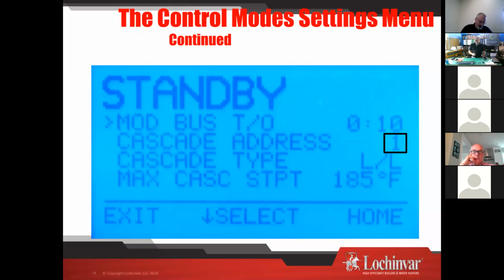But this is where you set it up. So Cascade address 1 is actually the first member boiler. 0 becomes the leader. Select your Cascade type, lead lag or efficiency optimized.